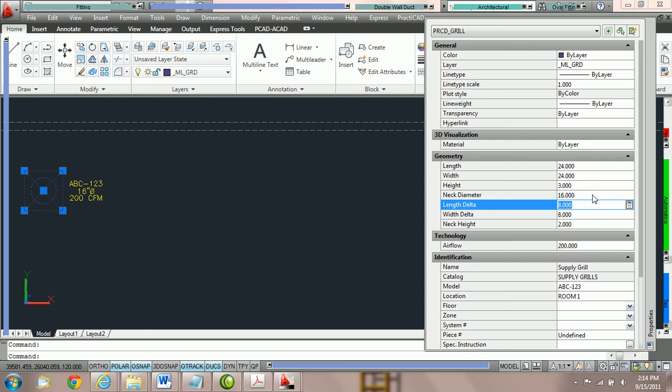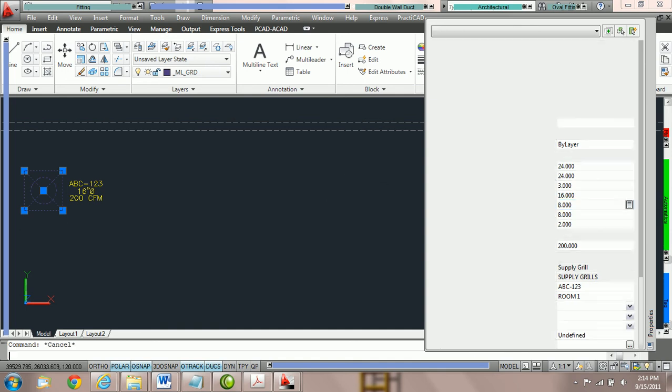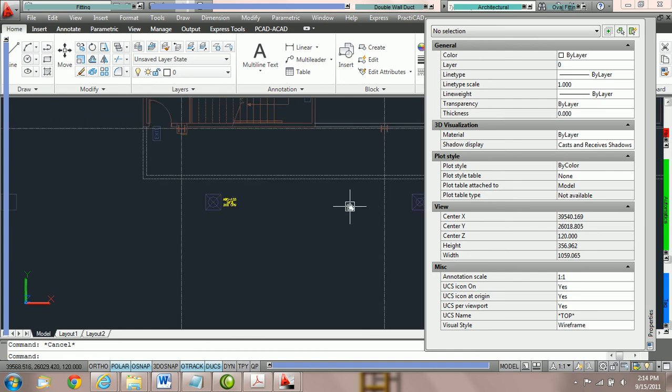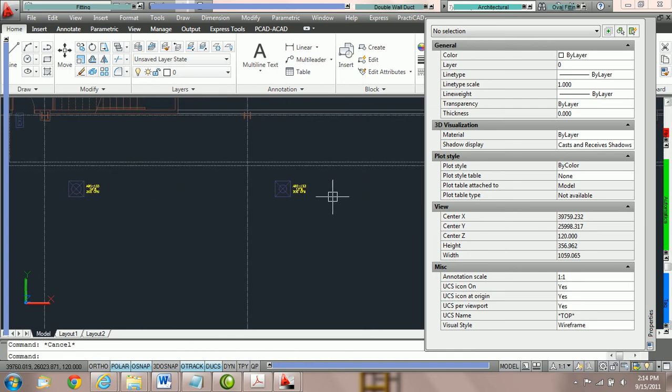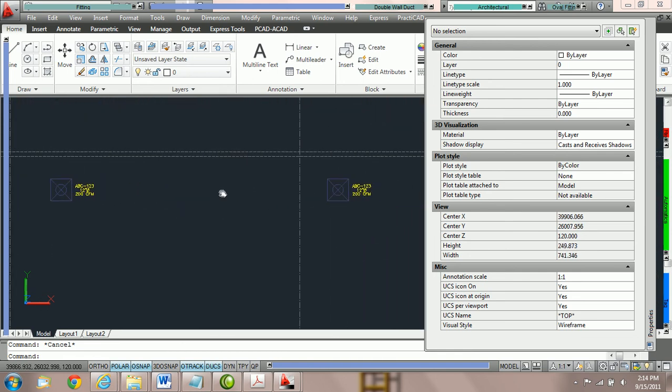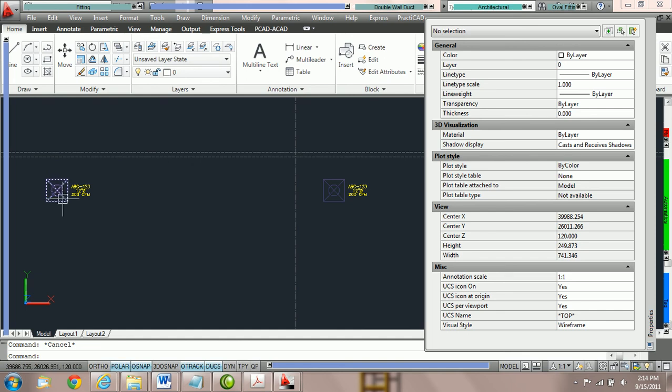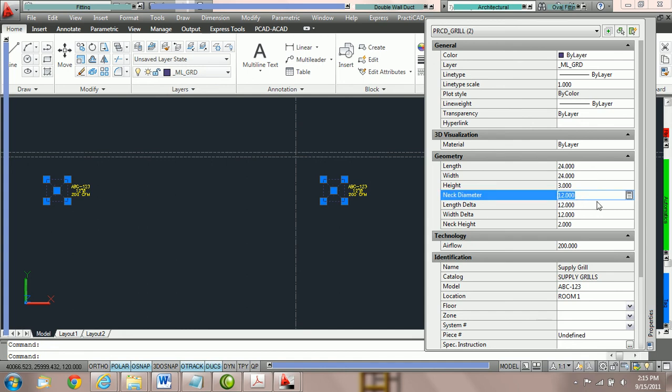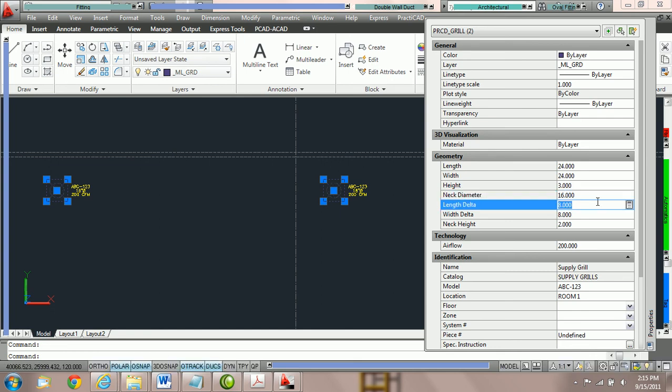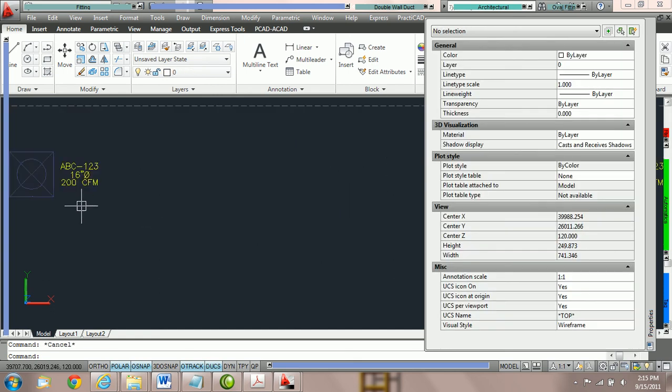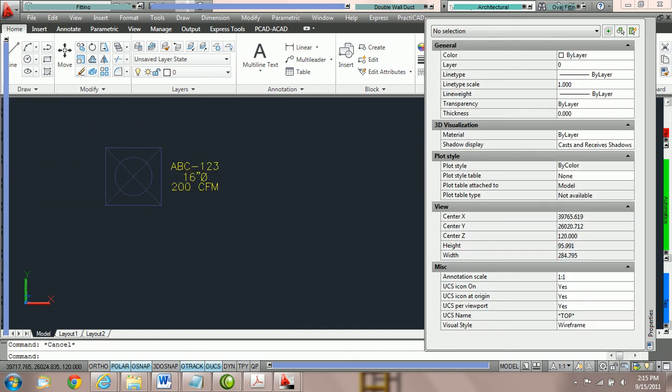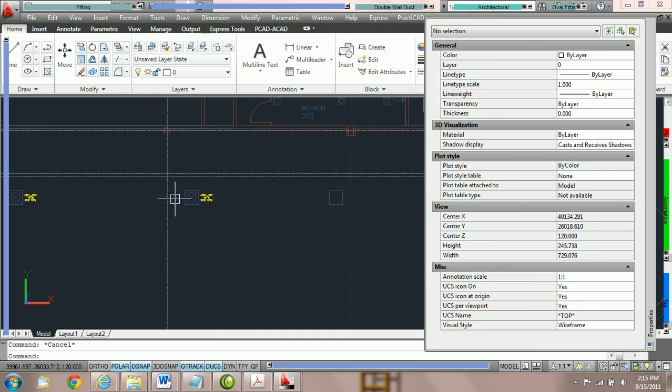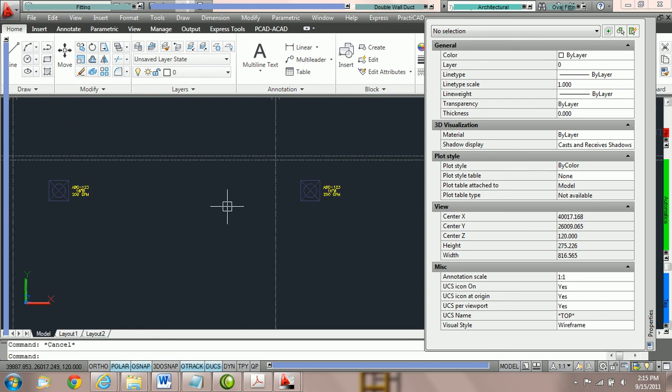You can also globally edit grills. What I mean is, since your grills are the same entity, you can actually edit more of them than one at a time. For example, click on one grill, and then select a second grill. Then open up your AutoCAD property box, and type in neck diameter 16, and hit enter. And you'll notice that PractiCAD will let you do this because they're the same entity. So now, PractiCAD has edited both, and your tags should update. Your tags might be different than the one on this tutorial, but your tags should always update to your change. So that's how to edit the grills.